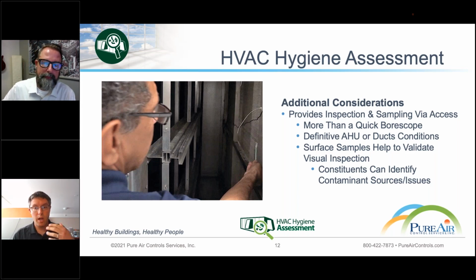Or vice versa, we have a lot of loading, a lot of particulate, and unfortunately a lot of mold growth. Let's confirm it, let's make sure, and use that to warrant that if we're going to invest in a ductwork cleaning or unit cleaning, it's actually needed. That's how we get more in depth with the units and confirm if something is suspect, and what multiple ways we can prove it: a visual, some sampling, and breaking things down. Not just one look, but multiple looks at the system, multiple components, and then putting that all into a bigger picture report with photographs and rankings, making it something tangible that can be used strategically.